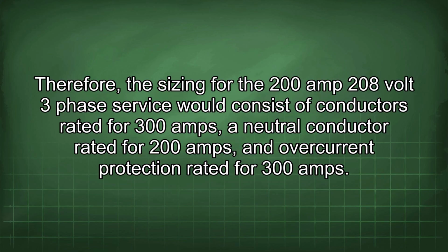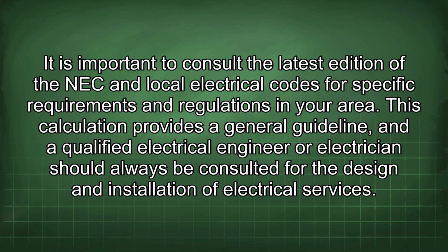Therefore, the sizing for the 200 amp 208 volt 3-phase service would consist of conductors rated for 300 amps, a neutral conductor rated for 200 amps, and overcurrent protection rated for 300 amps. It is important to consult the latest edition of the NEC and local electrical codes for specific requirements and regulations in your area. This calculation provides a general guideline, and a qualified electrical engineer or electrician should always be consulted for the design and installation of electrical services.